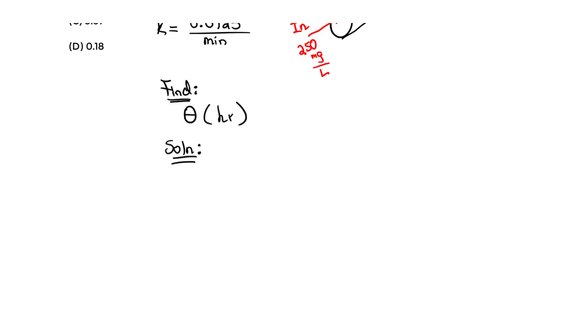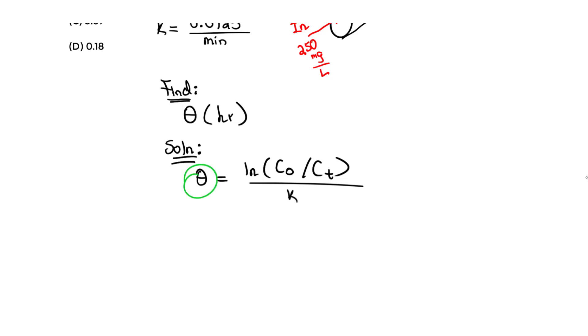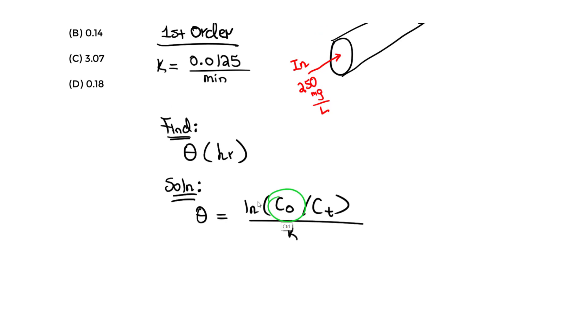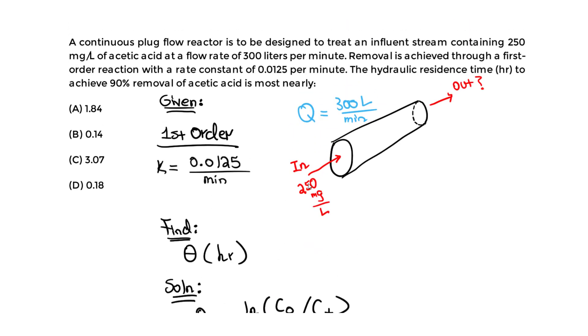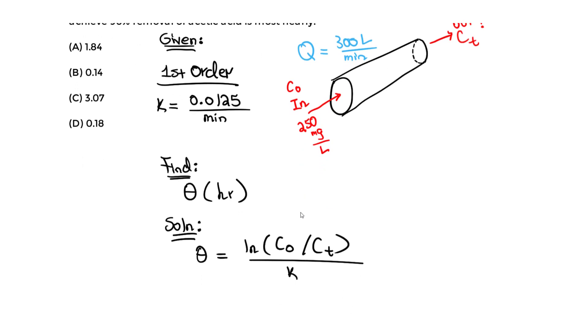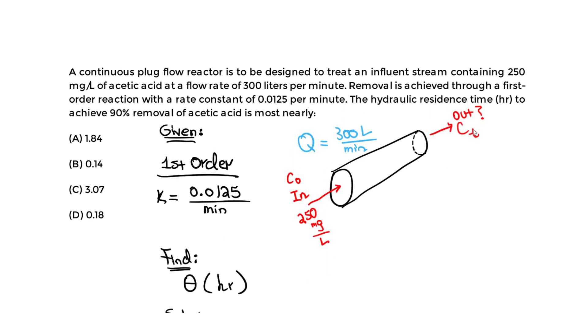The equation is: theta equals ln(C0 / CT) divided by the K value. Theta is the unknown — the hydraulic residence time. C0 is always your influent concentration, defined in the tables as initial or influent concentration. CT is your final condition or effluent concentration — what comes out of the plug flow reactor. So C0 is 250, and we need to determine CT.